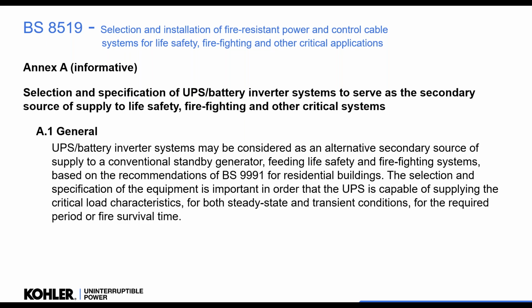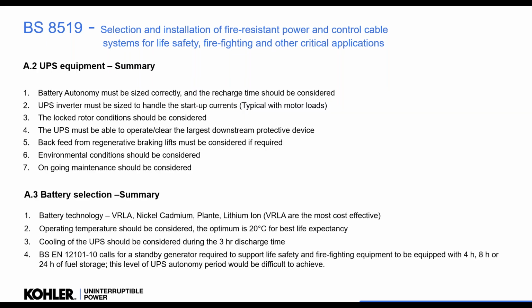So this is around selecting and specifying the UPS and some of the considerations we have to make. It talks about an alternative secondary source. It's conventionally a standby generator, but it can be a UPS, and according to 9991, if we look at, okay. So to summarize what Annex A talks about, the battery autonomy must be sized correctly and recharge time should be considered, because we have seen people just buying off-the-shelf UPSs with a short autonomy, saying, well, I've put a UPS on it as life safety, it's fine, when it isn't. We have to consider the recharge time, we'll talk about that.